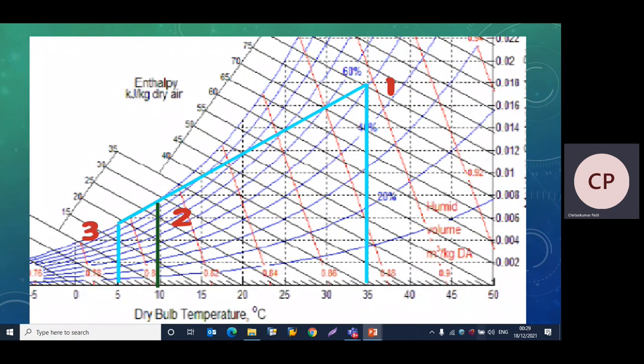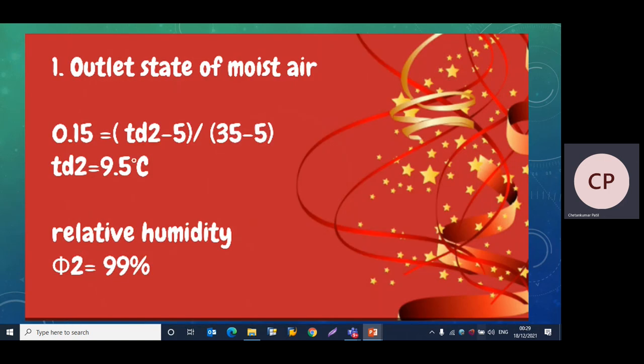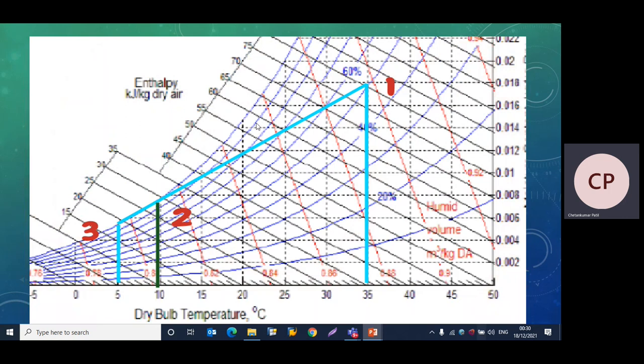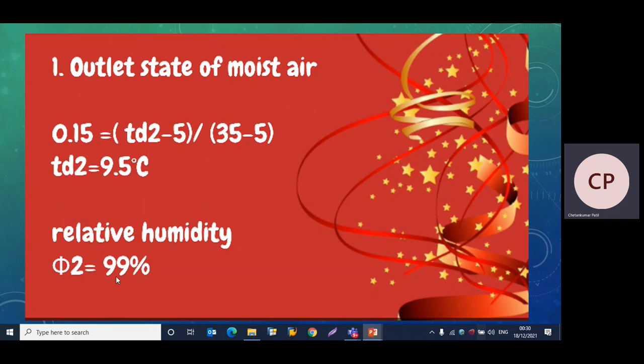We can now plot point 2. We take the dry bulb temperature of 9.5°C and extend this vertical line up to the line joining point 1 to point 3. The intersection gives us point 2. The outlet state of moist air at point 2 is: dry bulb temperature Td2 = 9.5°C and relative humidity ≈ 99%.